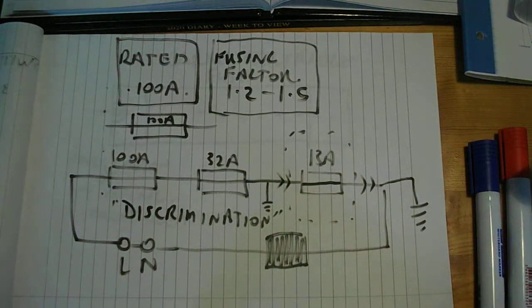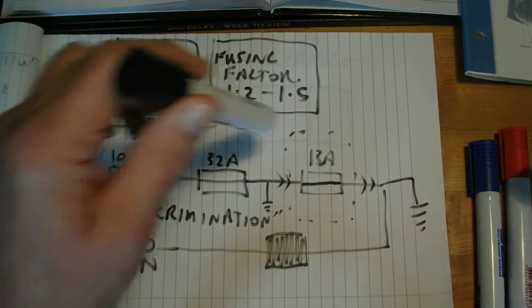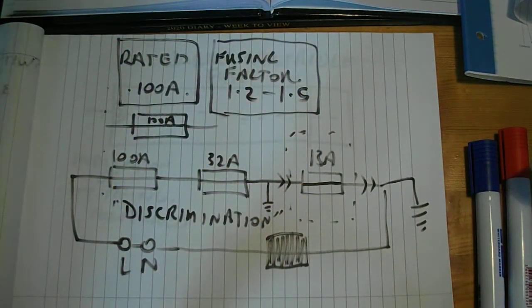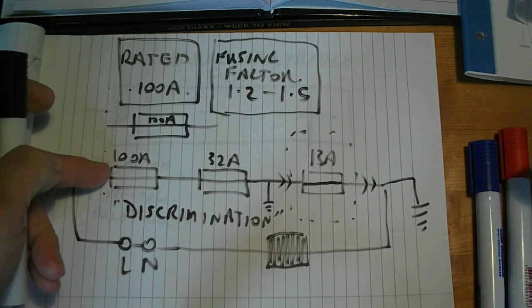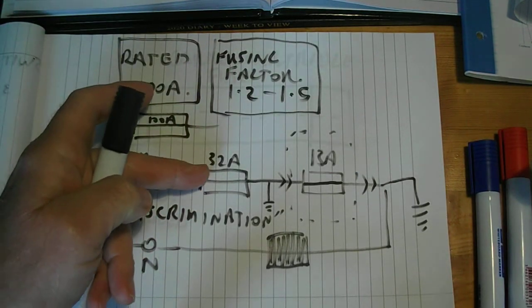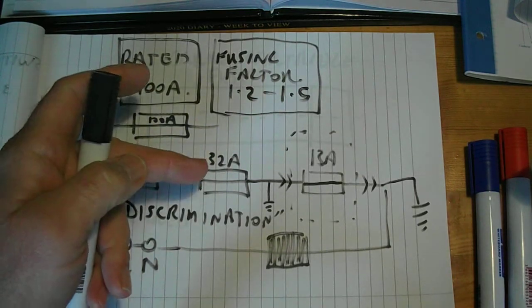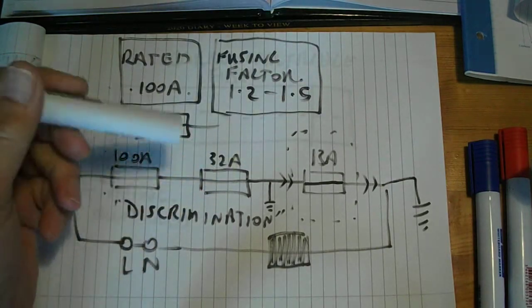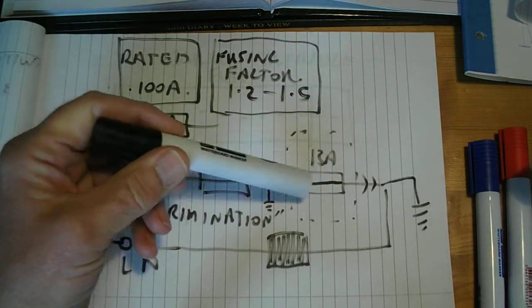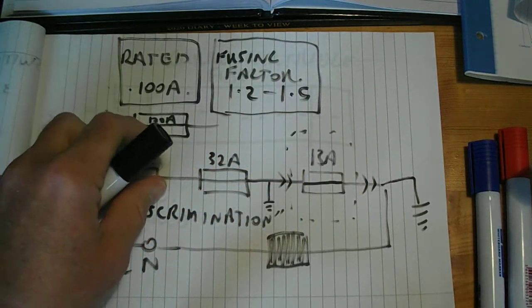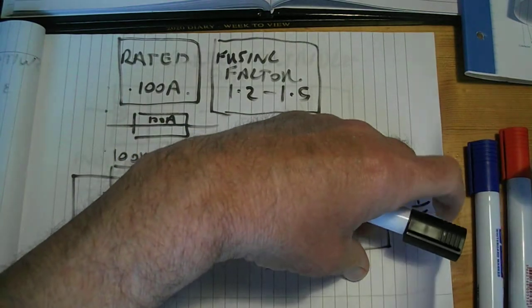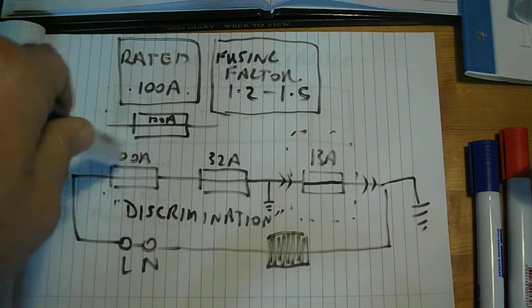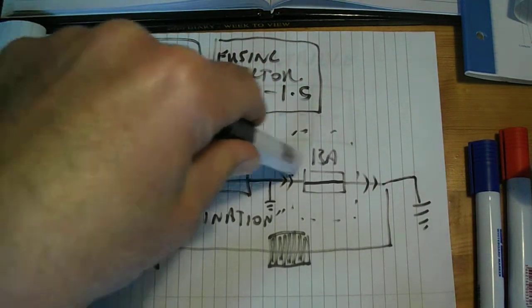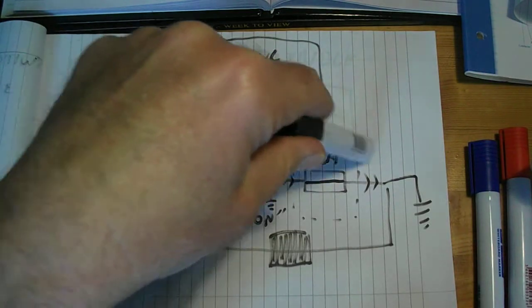Carrying on from discrimination of fusing. Remember, we have 3 fuses in series here. This represents the 100 amp fuse at the cutout, this represents a 32 amp fuse or circuit breaker in the consumer unit of a customer's property, and this 13 amp fuse is inside the plug top operating a domestic appliance. Discrimination means these fuses must be substantially different so that the one nearest the fault blows first.